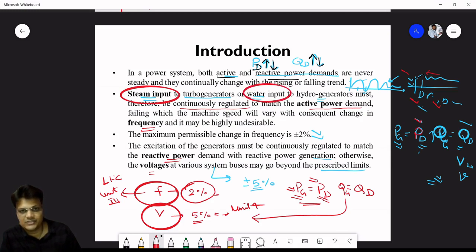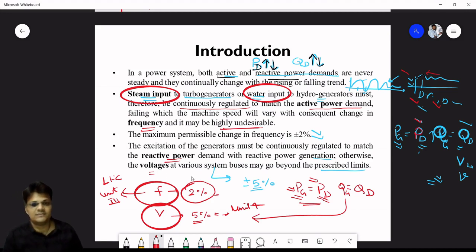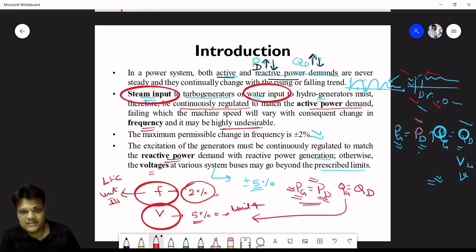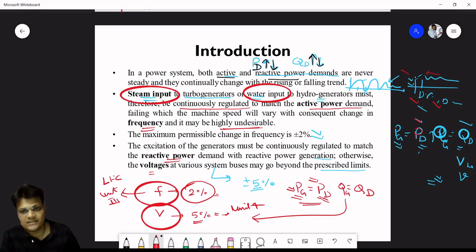Failing this regulation, the machine speed will vary with consequent change in frequency, which is highly undesirable. Similarly for reactive power demand, the excitation of the generator must be continuously regulated to match reactive power demand with reactive power generation.